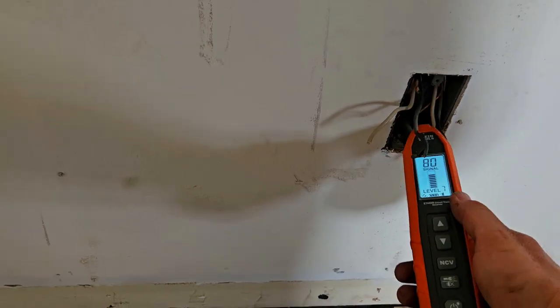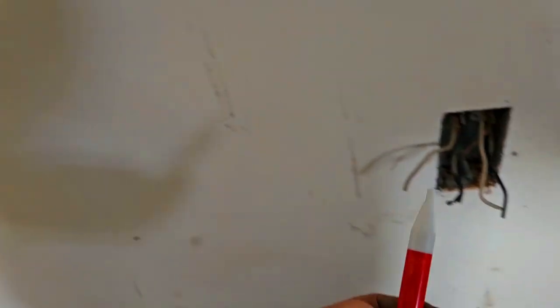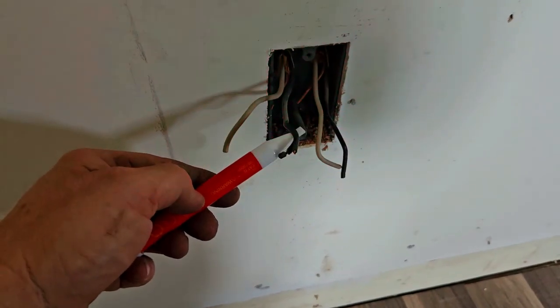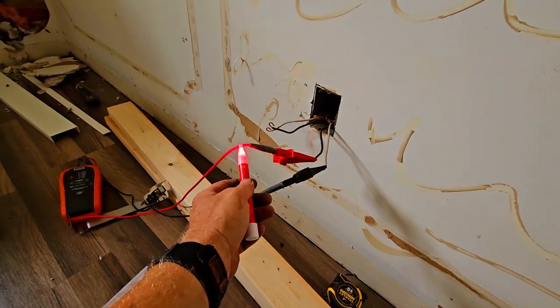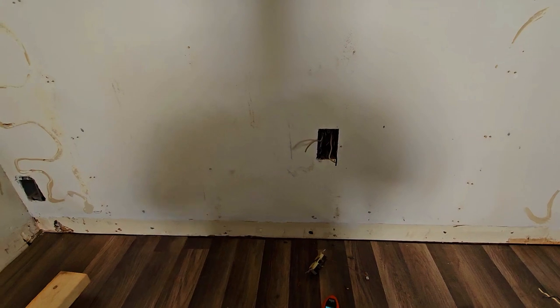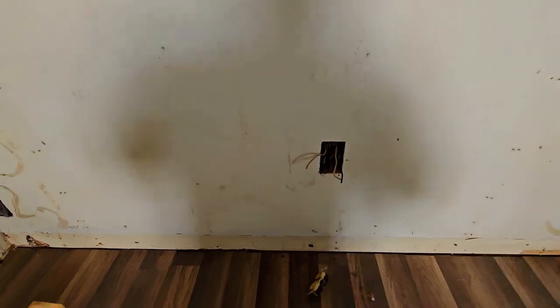So it reads pretty good. What I found out is that if you have your tracer — the transmitting part of it hooked up with the clip jumpers — you can take your tick tracer and it will show you which wire it is for sure. You see how it's sending a tone? Over here it's not doing anything — there is no power, the meter is completely out of this equation. But it does it over here, so it verifies that it's transmitting. So if you're in a place where there's computers or whatever and you need to find the exact wire among a whole bunch of wires, that's the best way to do it. Even though you think you're dead on, sometimes you're really not. Using this method, it's damn near perfect — it shows you exactly where it is.